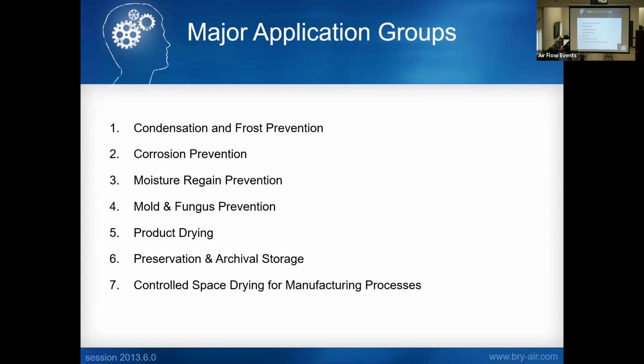So we look at whether it's a critical temperature control, and whether I want to keep the cost down on the post-cooling side. If it's lower moisture removal, we're talking 35% RH, 30% RH, I may choose to lower the reactivation heat source temperature to get colder air coming off to the process side of the unit.